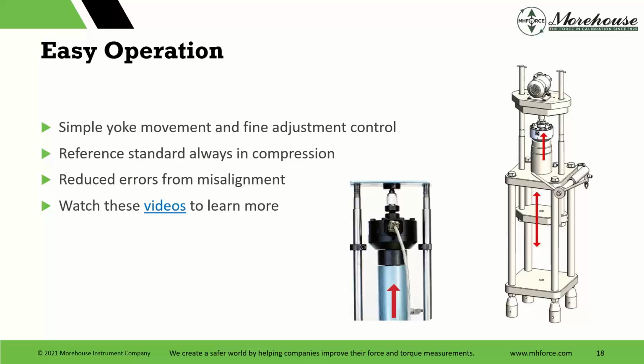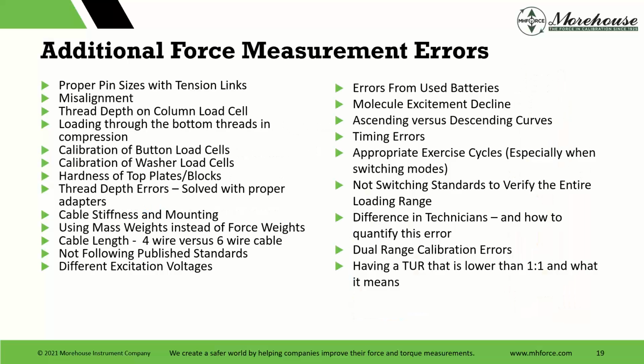When you switch from tension to compression, you really need to re-exercise the load cell. There are some other things with the process that may help you get better uncertainties if you just keep a load cell in compression only throughout its life cycle instead of both compression and tension. And then reduced errors from misalignment. That's the way we have it set up. The way it sits in that machine is exactly how it's calibrated, with those adapters and ball adapters. And we have a lot of videos here for anybody who wants to learn more about that.